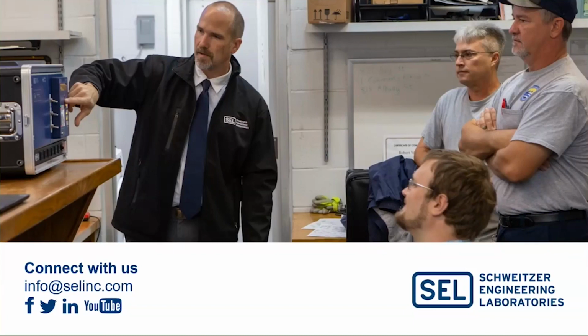So what we've done with the seal fail and thermal fail is we have logic you can use to interlock that to the pump runs and then annunciate it. It's more in the form of an application guide that you add that logic to, and your local application engineer is a great resource for seeing how that's done. I've helped numerous integrators put in that logic and test it, and I'd be glad to work with you directly — I can get you an existing settings file and walk you through what that looks like.